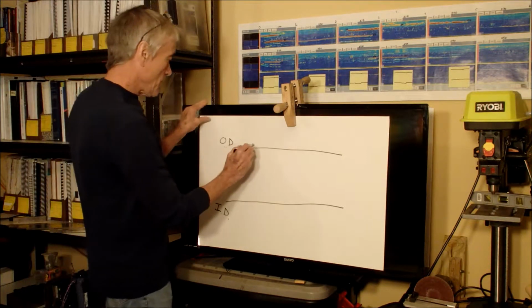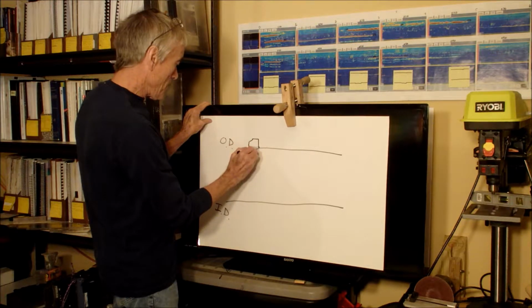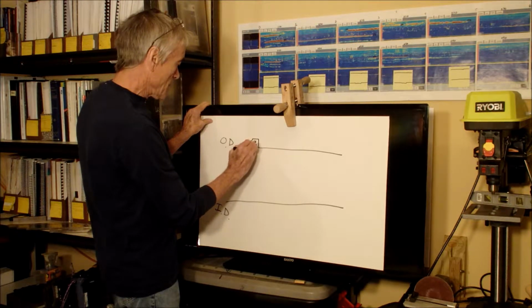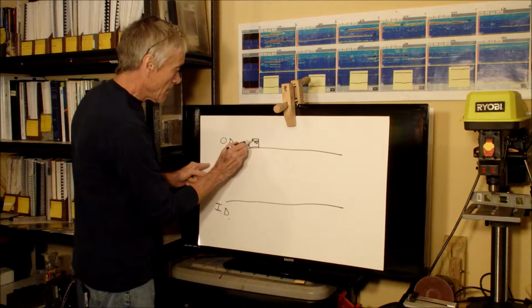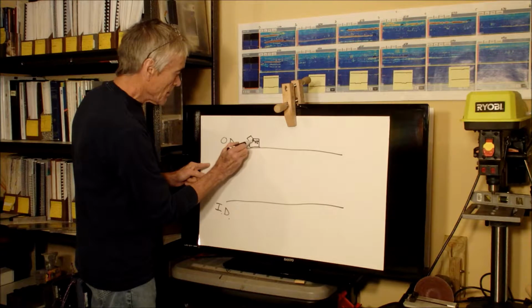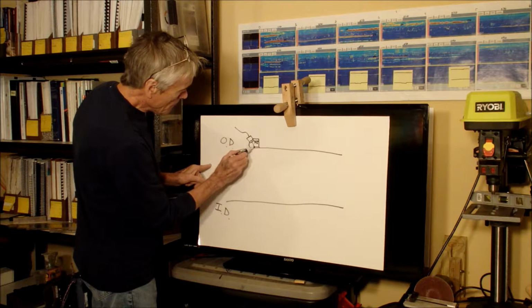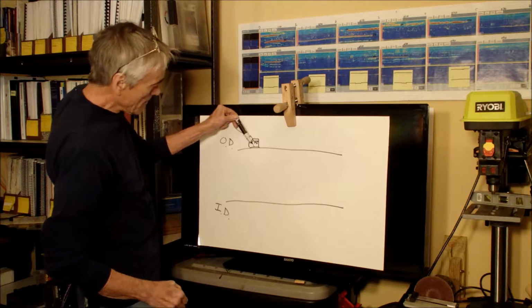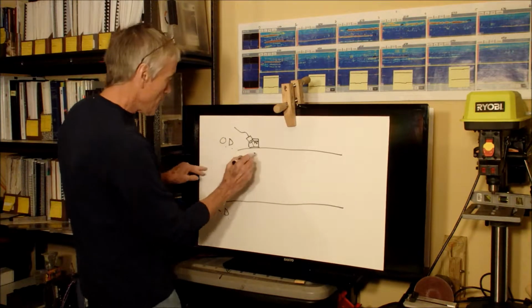And if we put an angle beam search unit on it, say for example that was the wedge for a 45 degree, and we had our transducer screwed into the wedge. I'm going to draw this as if the sound comes out of there as a laser beam, but really it's more like a shotgun blast of sound.